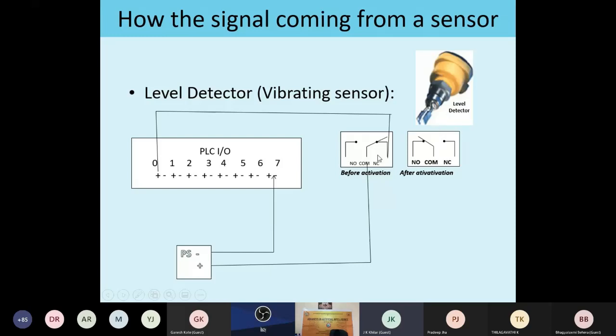So how is the signal coming from the sensor? In the sensor there are two contacts, one is the NC contact and one is the NO contact. Suppose I have connected my level sensor at the NC contact. NC contact means the PLC plus will be connected here at NC, and the power supply plus is connected to the common point. Now this NC is connected to the PLC. Now when the level is not reached, the PLC is getting a plus signal, that is 24 volt. Maybe 230 volt, maybe 110 volt, depending upon the PLC card or the sensor, we are sending the data to the PLCs. PLC has some 24 volt cards, also 230 volt or 110 volt cards.